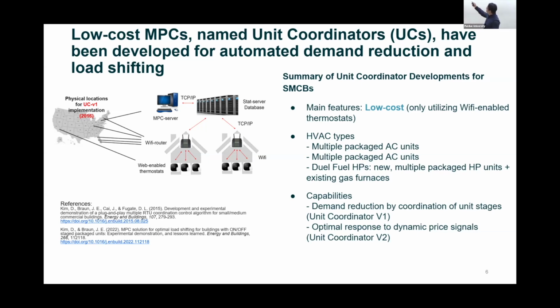predictive control. The reason why we wanted to say a low-cost MPC is that we are using only the web-enabled thermostat, not an expensive building management system deployment, for small and medium commercial buildings. So by doing that, this is the architecture that we have extended. Originally, it was developed only for the AC rooftop unit, but we extended it to the heat pump and then to the dual fuel heat pump. I will talk about that later.